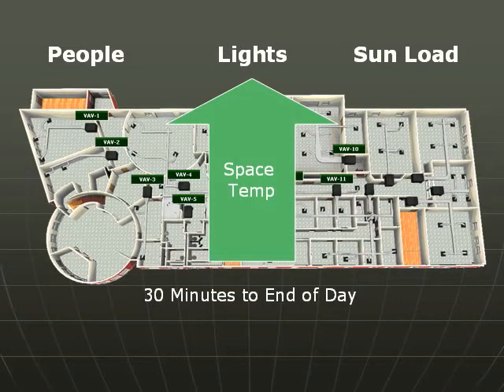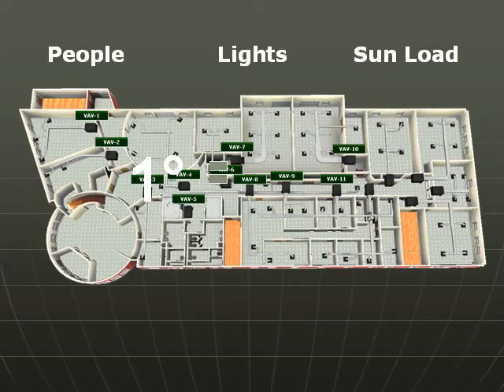A 1 or 2 degree increase in the tenant's set point right before they leave is an acceptable adjustment in the air-conditioned environment. 1 degree can have a 3% decrease in your mechanical energy consumption.